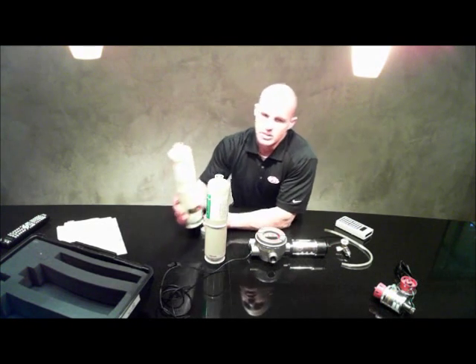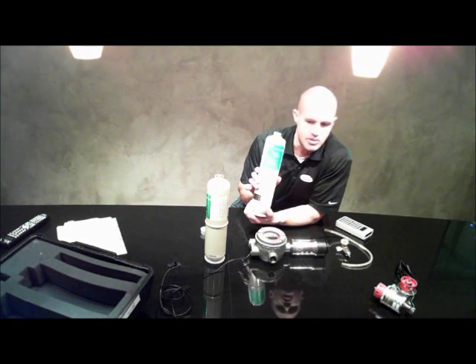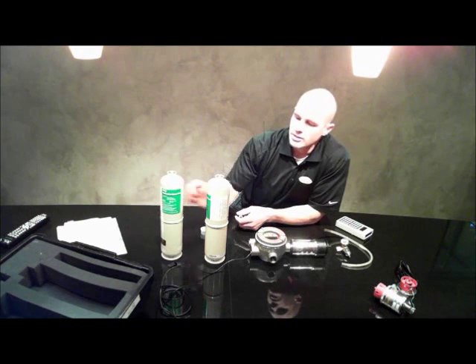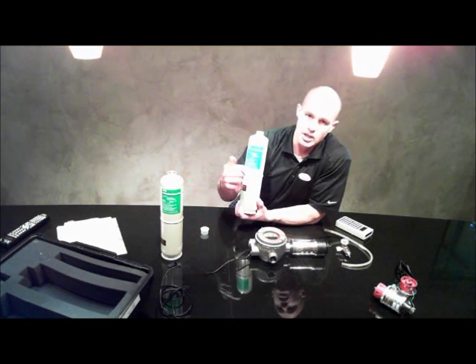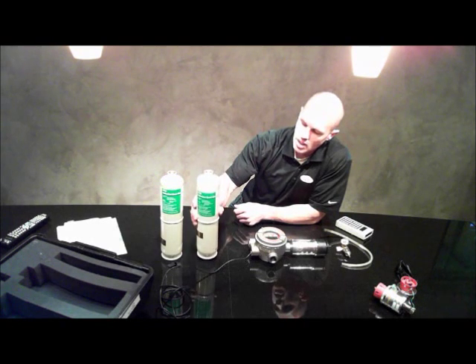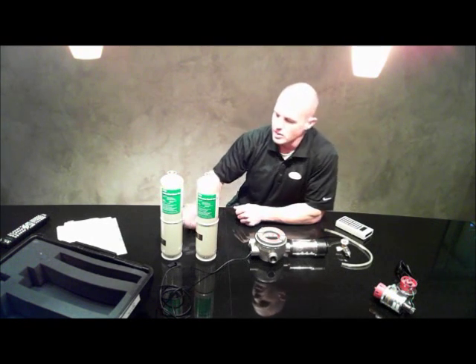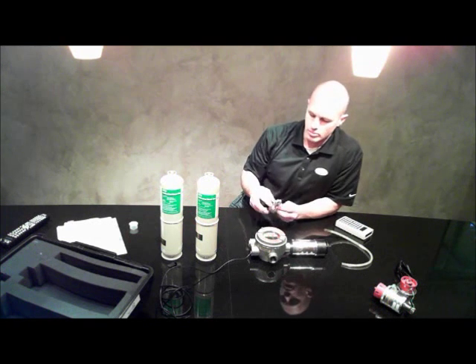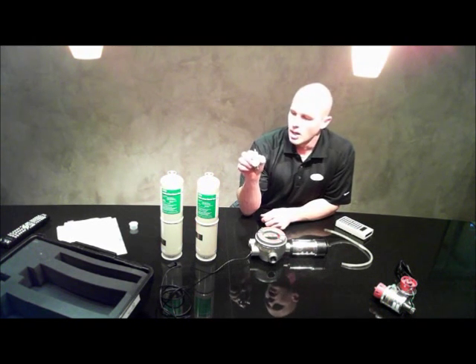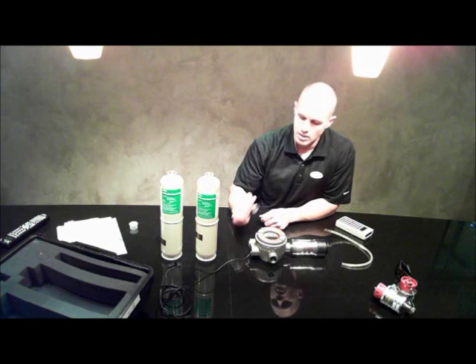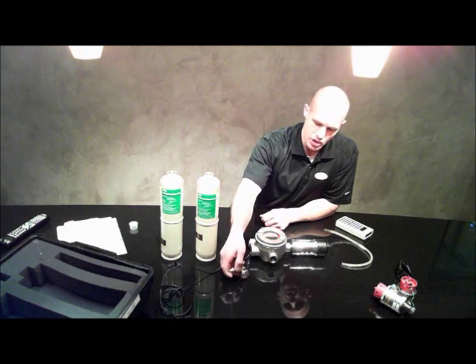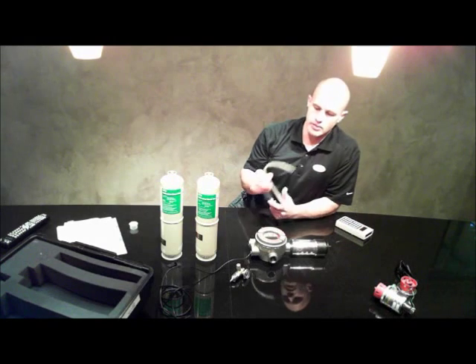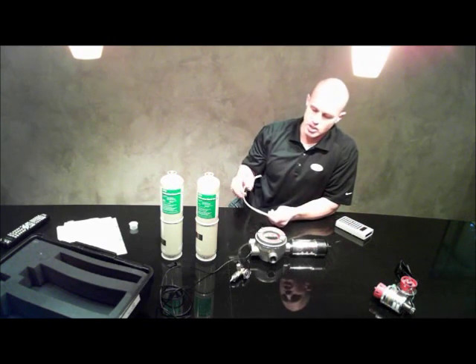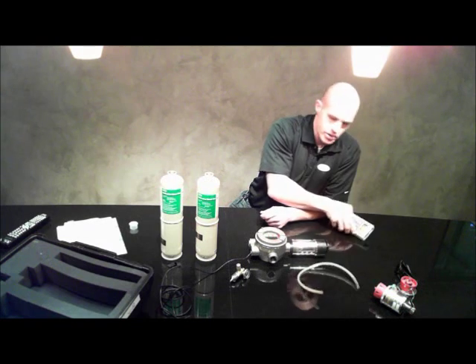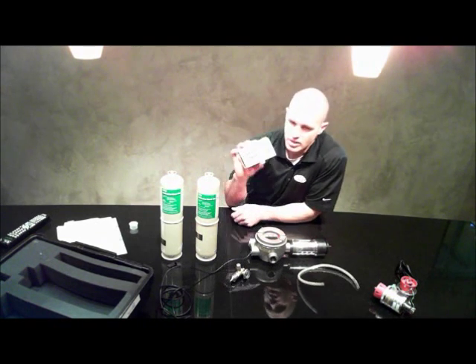I've got my calibration gases. This is oxygen and nitrogen, so my zero air. This is methane, since I'm going to be calibrating a methane sensor. And then for both bottles of gas, I've got a 1.5 liter per minute regulator to regulate the gas for the calibration, and the tubing for the regulator onto the calibration cap here. And then also important to the equation is the controller.